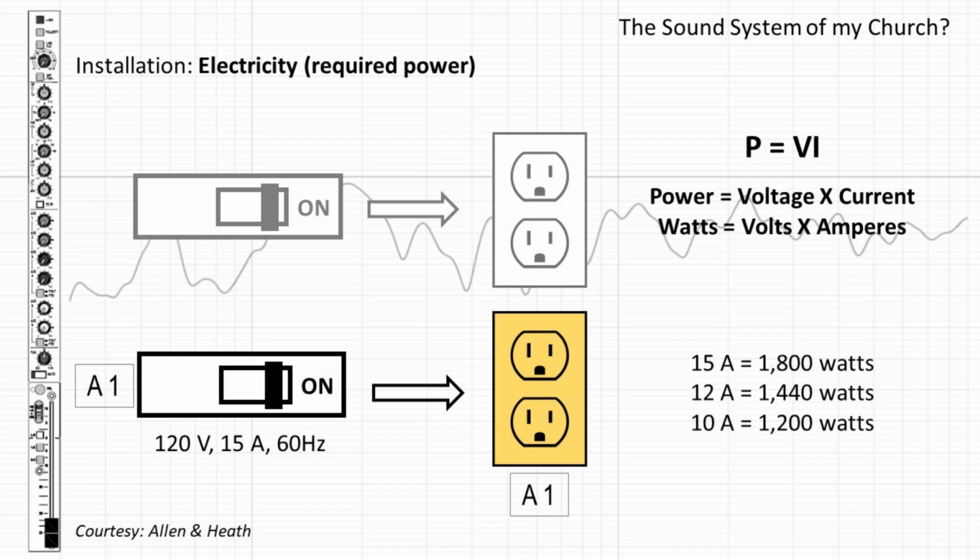Power requirement. My advice is to use several specific electrical outlets of different colors on separate dedicated circuits and breakers for the AVL equipment. You should be able to make the evaluation of your electrical needs. The simple formula is power in watts equals voltage times current. A 15 amps circuit offers a very maximum of 1,800 watts.